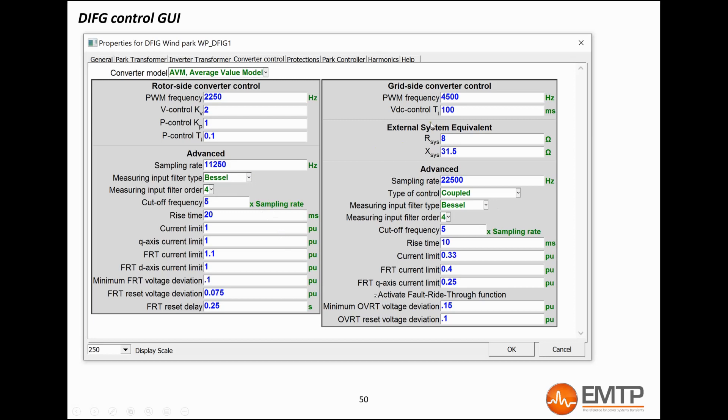The external system equivalent is important to set up as, like I explained a few slides ago, the grid-side converter inner loop gains are calculated using this information. The turbine might become unstable if this data is unset properly.